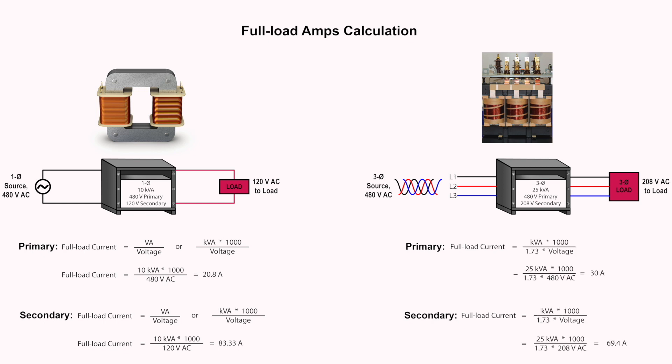Next, we have a 3-phase 25 kilovolt amp transformer rated 480 volts primary and 208 volts secondary. Using the full load current equation, the primary and secondary full load current are calculated as follows.